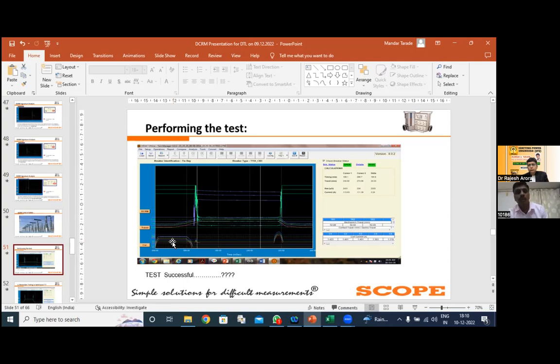Accordingly, we can comment on the health of the coil current. We are performing the insulation test also. This is basically a successful test. We have received all the 3 coil currents for the closing, all the 3 coil currents for the tripping.